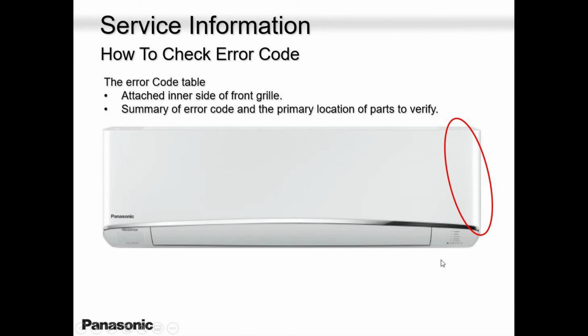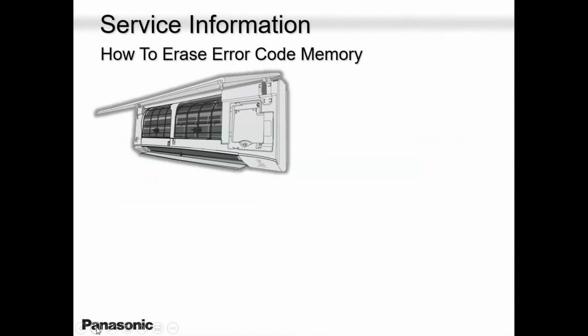If you're not sure, maybe you skipped it, you can go back and forth. You can go through all the error codes and come back again. The beauty about our unit and all our units, they store only one error code, the latest error code. So please don't go to job sites for service maintenance or monthly or yearly maintenance and start pulling error codes even though the unit is running. You may end up pulling an error code that was stored before and got rectified and was not erased. So only pull error codes when the timer light is flashing, guys.